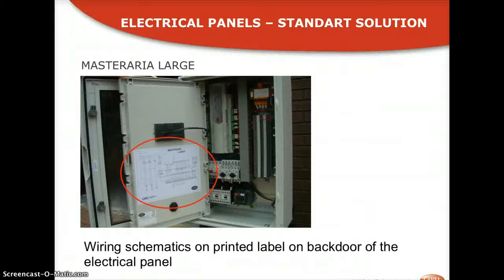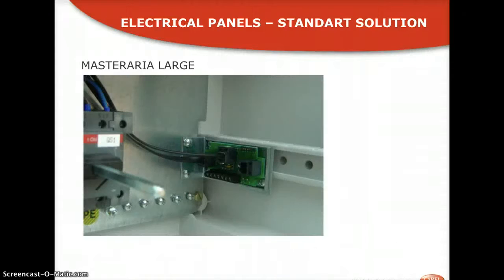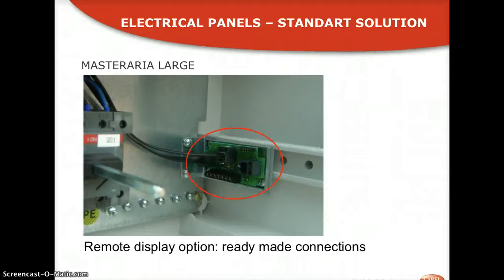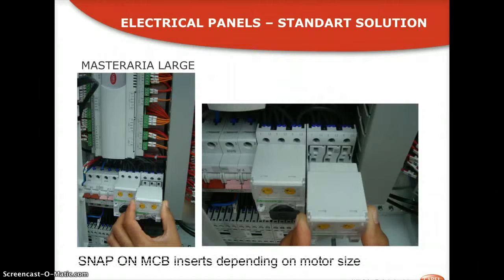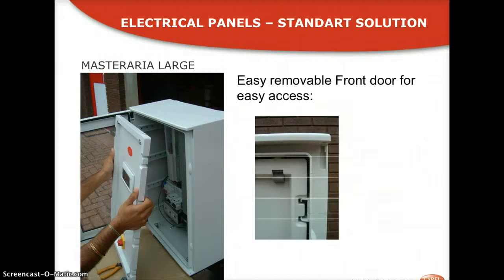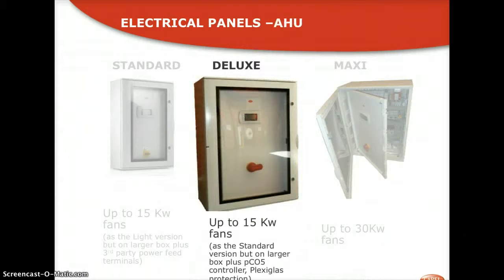There is a wiring diagram sticker stuck on the door of the panel, so you don't get the bad luck of losing it. On the right hand side of the door you will find the splitter for a remote display connection. Here you see the snap-on MCB inserts, which are optional because you can select the appropriate size that will match the exact power consumption of your fans. The door can be completely removed, and that is all about the Masteraria Standard.